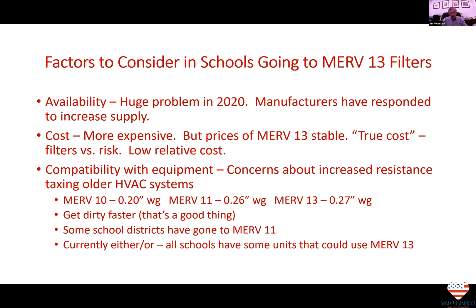If you look at MERV 10, MERV 11, and MERV 13, all three are relatively close in resistance. So if you're using pleated, well-made filters, compatibility is not as much of a concern as it has been made out to be. The MERV 13 gets dirty faster — you'll have to change it out faster — but that's what you're trying to do with a filter; it's a good thing that the filter is getting dirty. Some school districts have gone to MERV 11, which is perfectly acceptable and a good alternative. MERV 11 is certainly better than a MERV 8 or MERV 10.